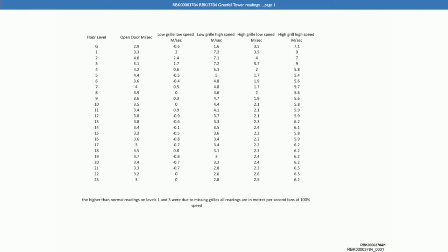Now, a point that I think you make at paragraph 74 on page 15 of your latest witness statement is that if you went for example, 51% of the level 4 data, 51% being, I think, what Dr. Lane's second scenario and how much... The maximum window failure scenario, yeah. Then that would be 4.2 metres per second down to 2.14 metres per second. So you make the point that for level 4, you'd still get more than 2 metres per second through the stair door, yes? Yeah, and I think that's on the bar chart diagram you had just now.